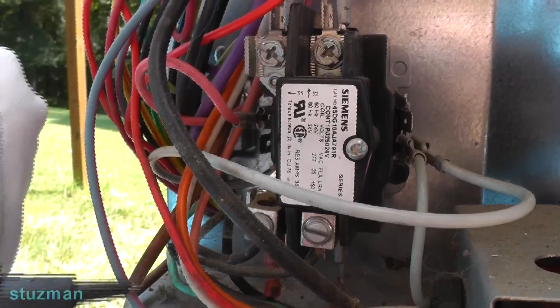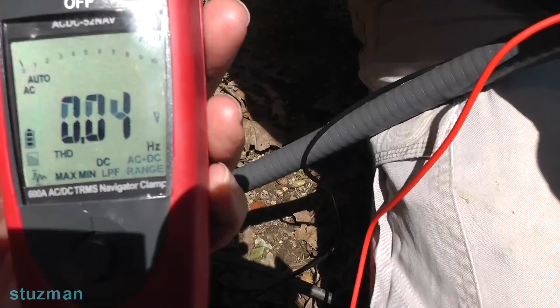The first thing I'm going to do is check on these two lugs on this contactor - this is where the line power is coming in. So between here and here, if this was on, I would have 240 volts. So as you see, I got 0.04 volts.